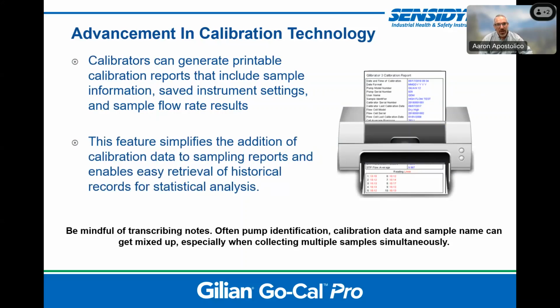I further wanted to discuss the calibration report. So the calibrators store that sample information along with the user input data and put it into a calibration log. Now this feature simplifies the addition of calibration data to your air sampling report and enables easy retrieval of historical records for statistical analysis. And as someone who has performed years and years of field sampling, it's important to be mindful of transcribing notes. Often pump identification, calibration data, and sample name can get mixed up, especially when collecting multiple samples simultaneously.